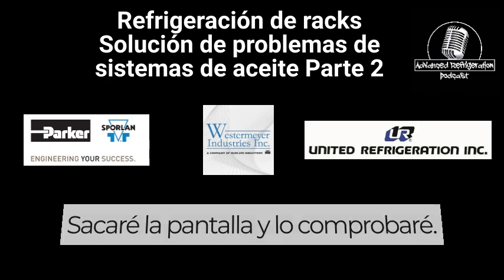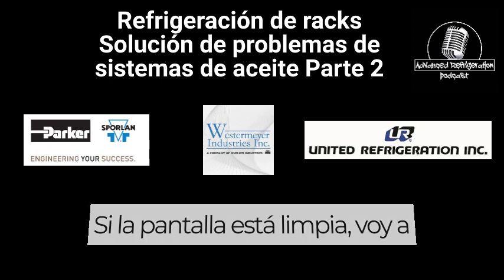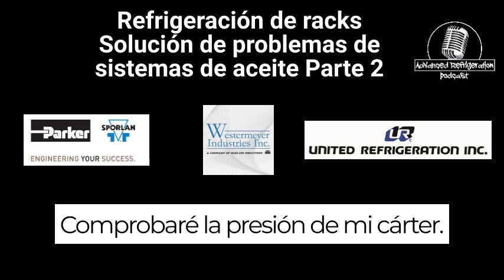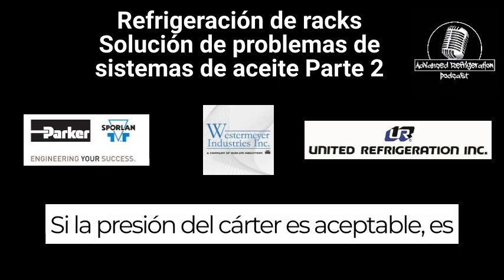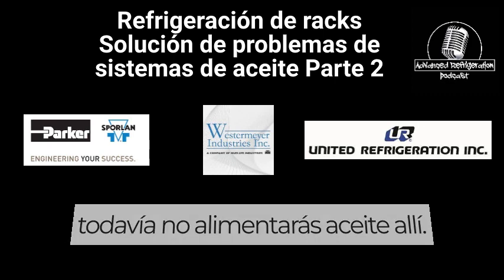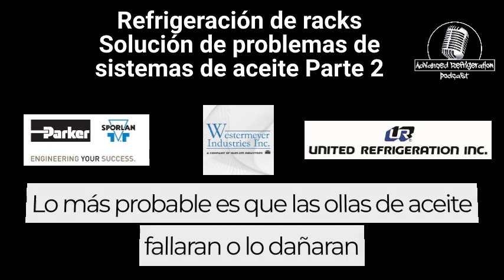On the inlet, I'll pull the screen and check it. If the screen is clean, I'll start the compressor back up. I will check my crankcase pressure. If the crankcase pressure is acceptable, it's the same as the suction pressure, and you still won't feed oil into there, more likely the oil pot's failed or it damaged it.